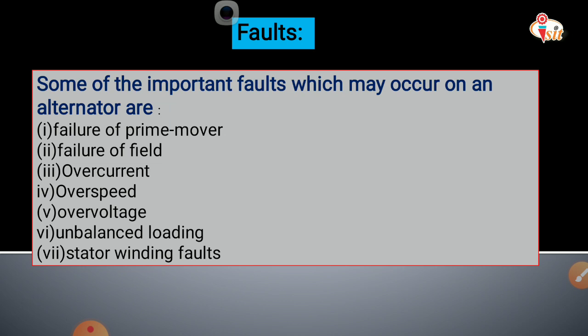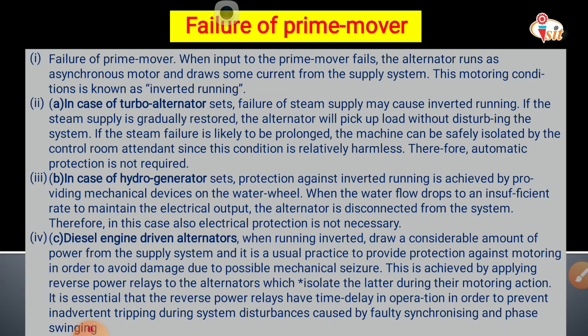The first fault is failure of the prime mover. When the input to the prime mover fails, the alternator runs as a synchronous motor and draws some current from the supply system. This motoring condition is known as inverted running.